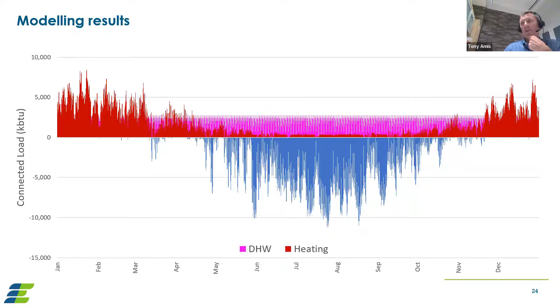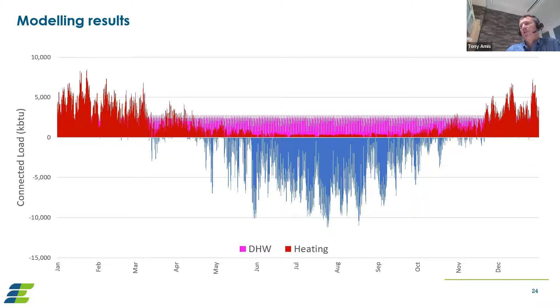From that, you can determine: can we deliver simultaneous heating and cooling? Where we're delivering cooling, the resultant heat can be pushed back into the heating circuits, maybe for hot water. One of the beauties of geothermal systems is that opportunity for simultaneous load, and that's one of the areas where you really push the energy savings significantly.